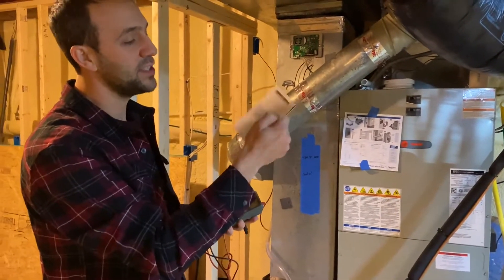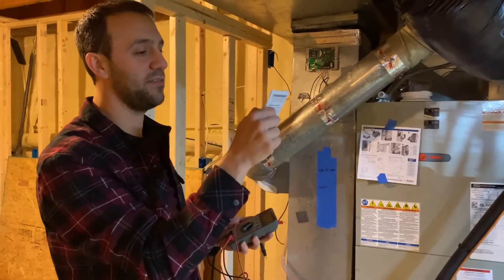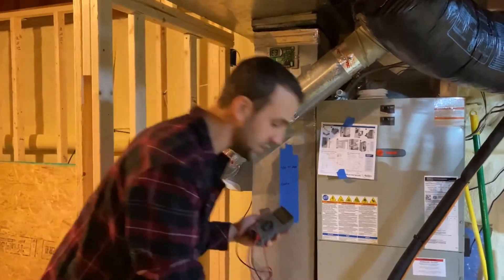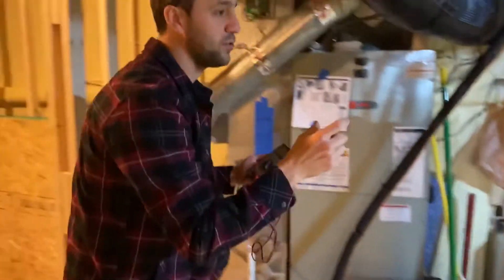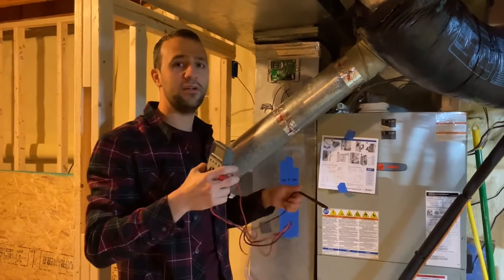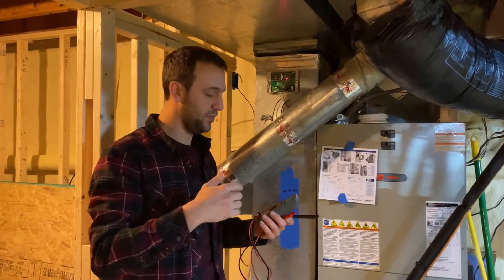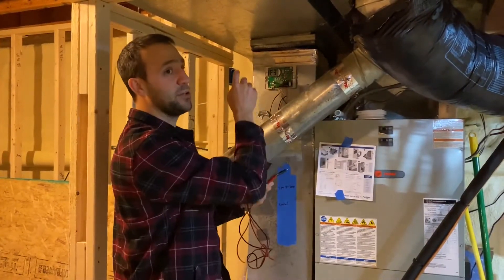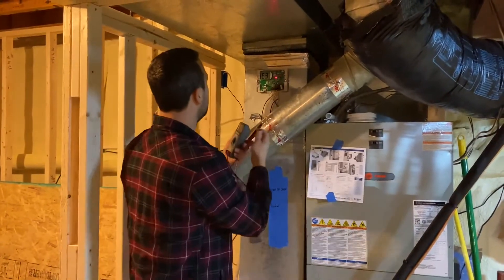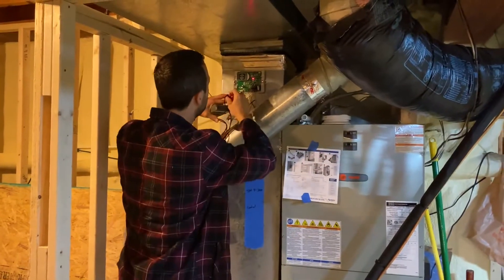We also need this resistance table — I'll put a link to it below. We need to know what the outdoor temperature is. Here it's 47°F, so according to the table I need around 23 ohms of resistance. There's an outdoor thermistor, and depending on the temperature outside, the resistance goes up or down. That's what controls the system and tells it how much heat to add.